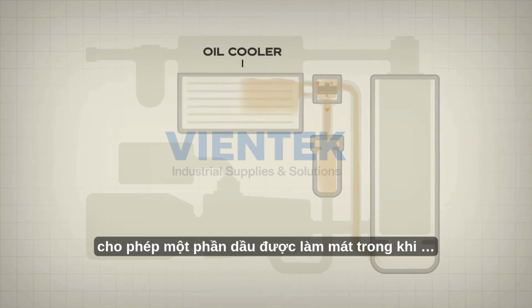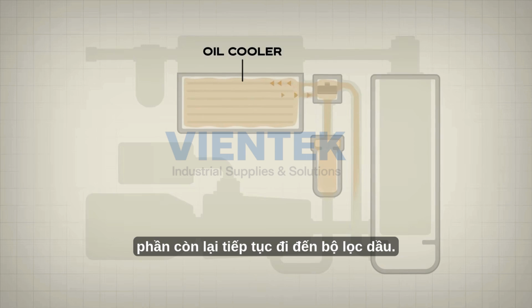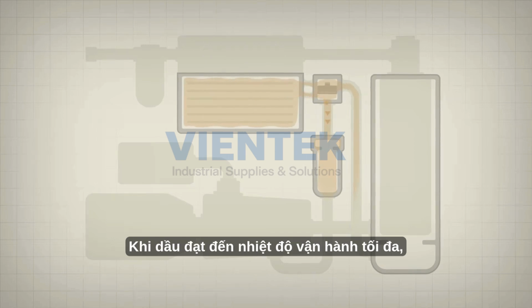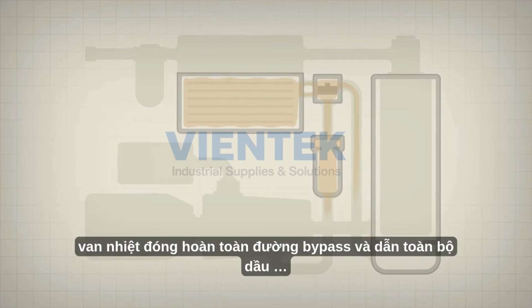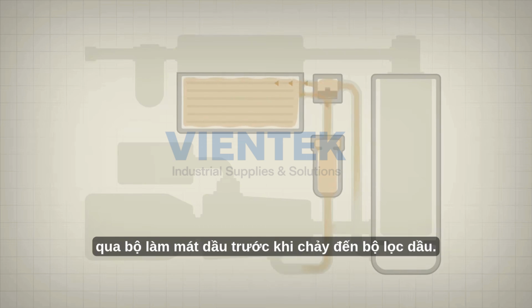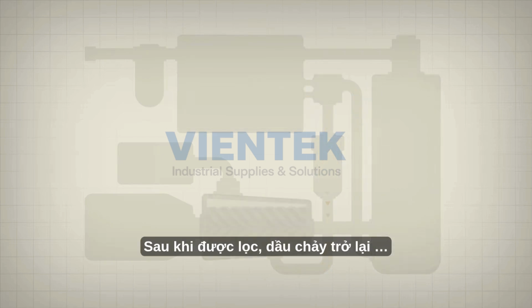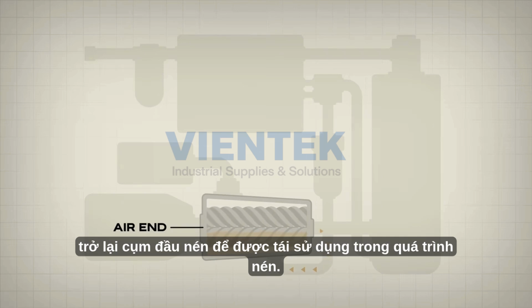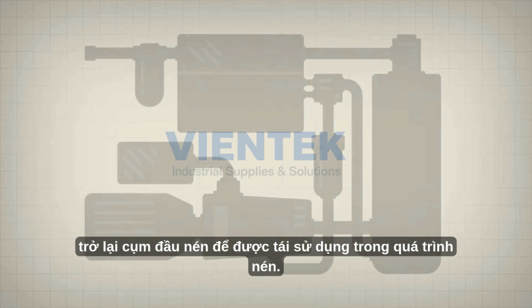path to the oil cooler, allowing a portion of the oil to be cooled while the rest continues to the oil filter. Once the oil reaches maximum operating temperature, the thermal valve fully closes the bypass and routes all oil through the oil cooler before it flows to the oil filter. Once filtered, the oil flows back to the air end to be reused in the compression process.